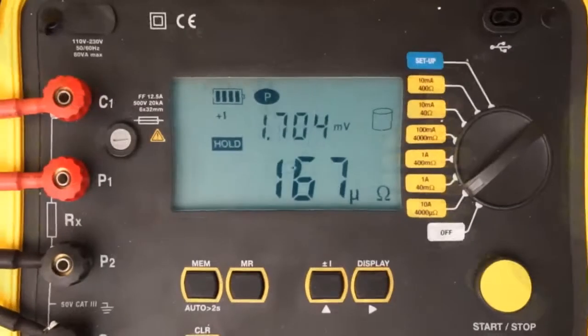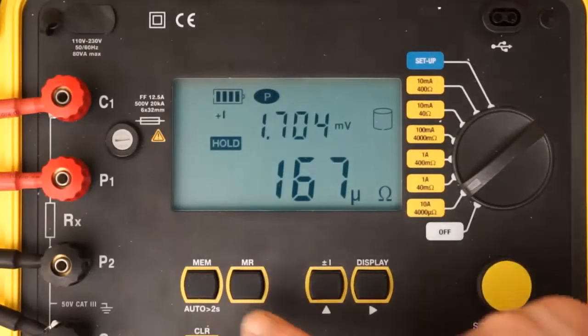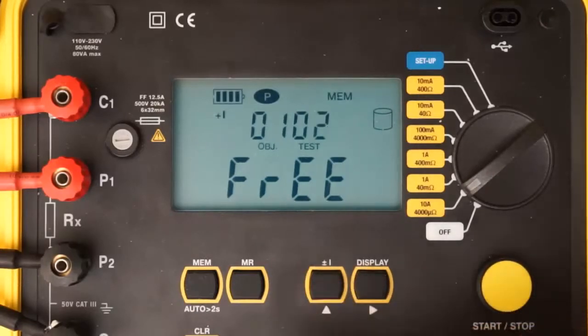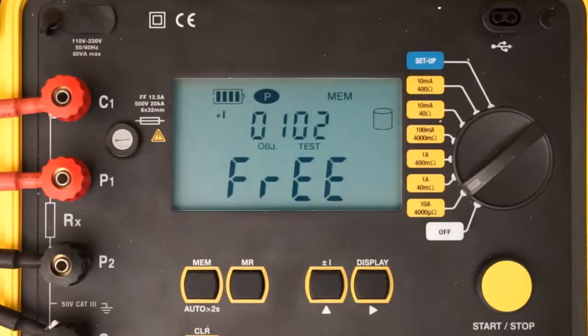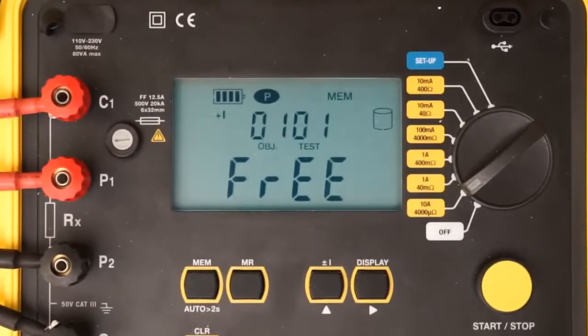To save the stopped test in the instrument's memory, press the memory button. This displays the default object number and test number under which this test will be saved. An object can contain multiple tests, similar to a folder containing multiple files. You can accept the displayed object and test numbers, or change them by pressing the up button, and then using the up and right buttons to make changes. To save the test to memory, press the memory button and hold it down until the word done appears.